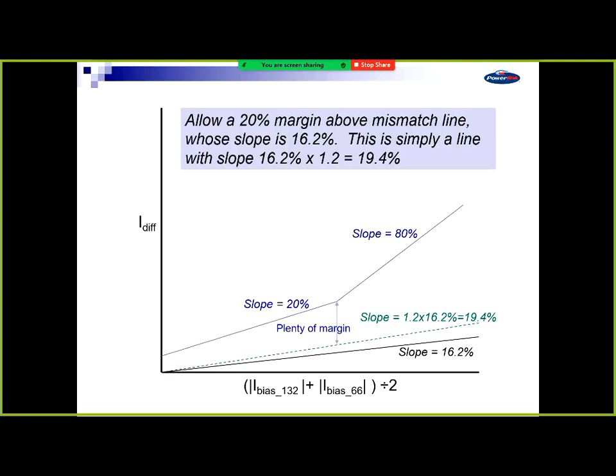The other thing there is that pickup at the bottom is not mentioned here. That'd be 25%. You've set your relay. You can see that bias down the bottom, or restraint, stabilised, all of those words mean the same, is divided by 2. That's where you've got to look at the relay manufacturer, what they're doing in their relay, how they're working that out.